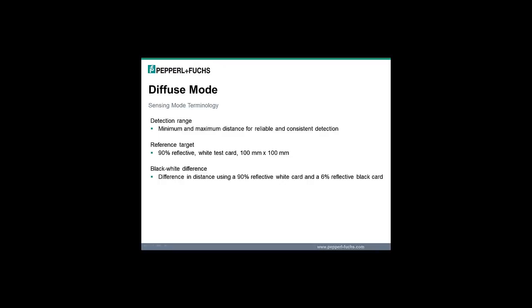Common terms found on the data sheet for a diffuse mode sensor: the detection range is the minimum and maximum distance for reliable and consistent detection of a reference target — a 90% reflective white test card that is 100mm by 100mm in size. The black-white difference is the difference in detection distance using a 90% reflective white card and a 6% reflective black card under the same conditions.